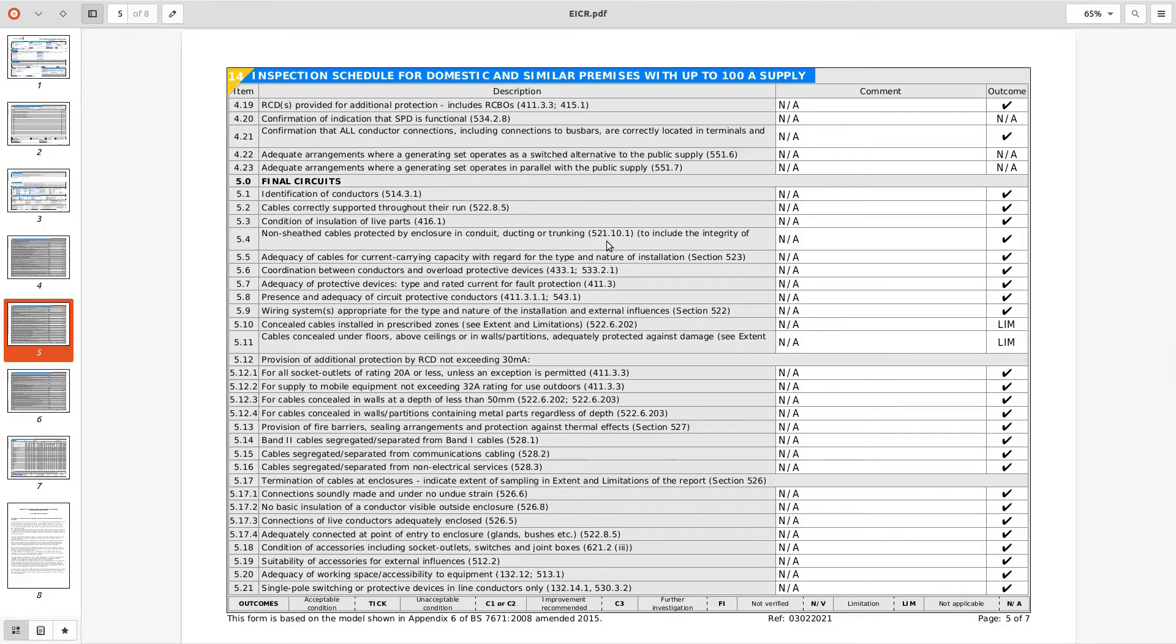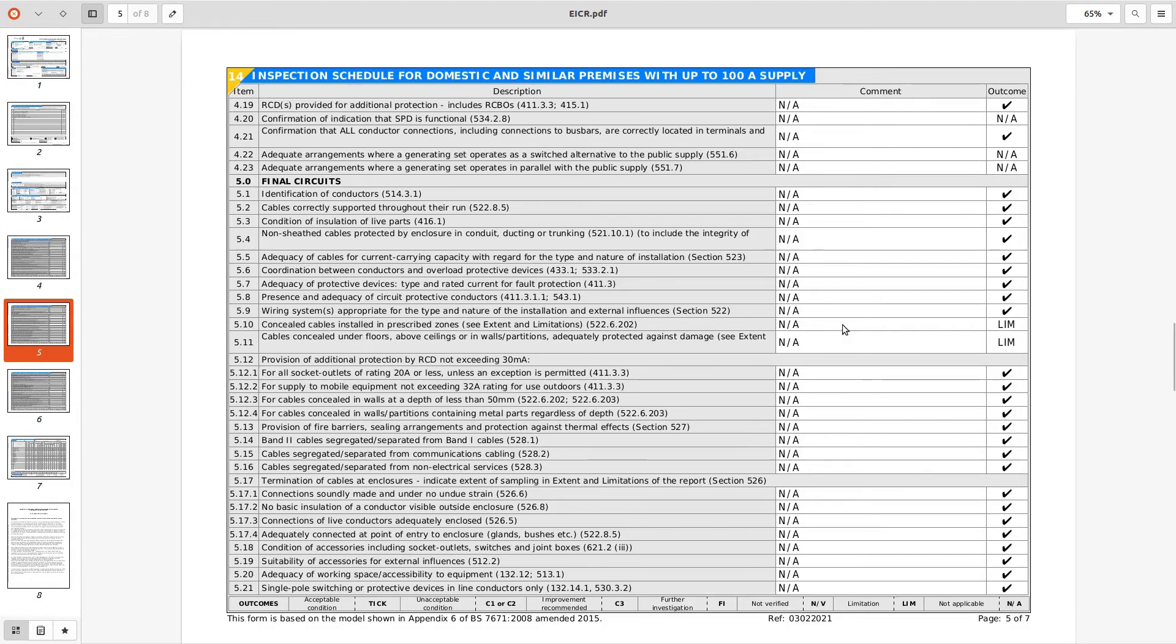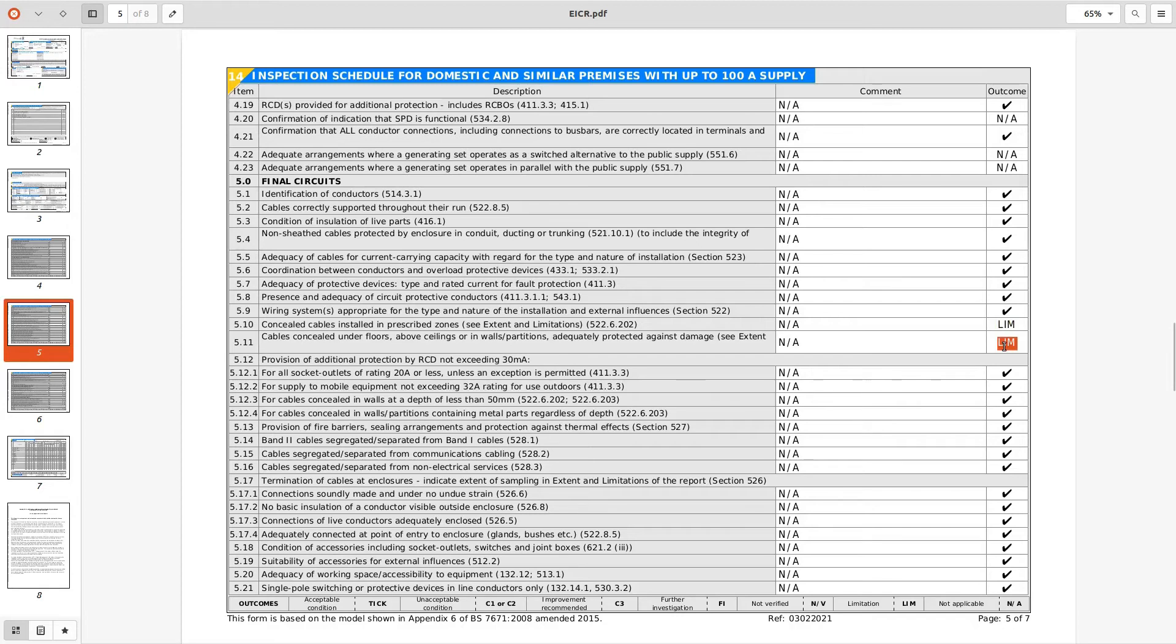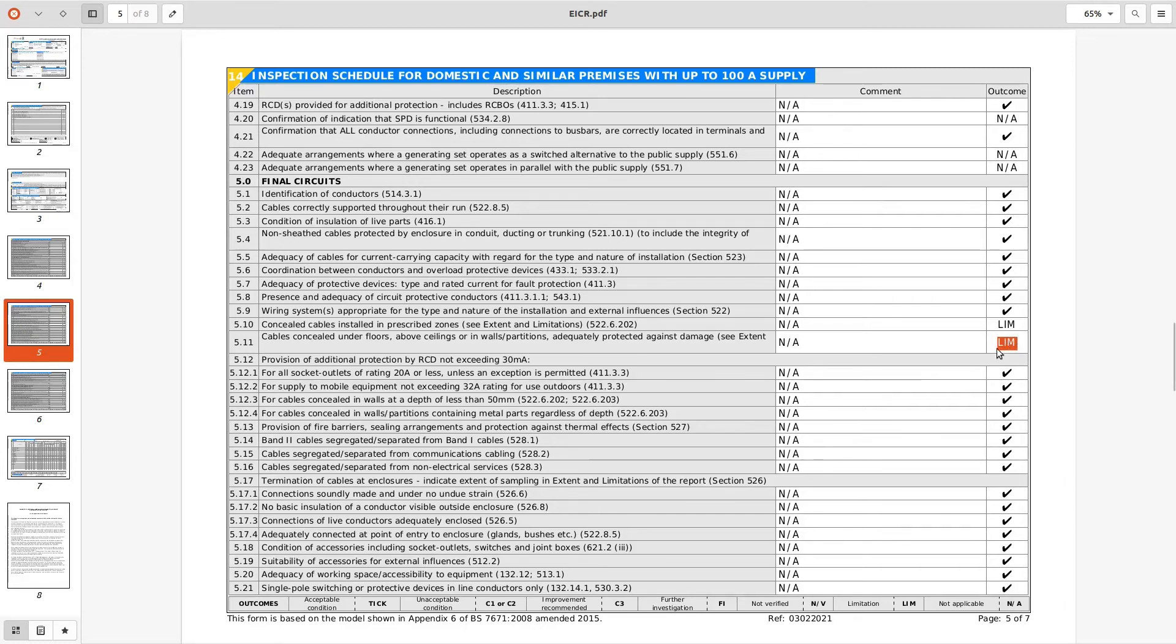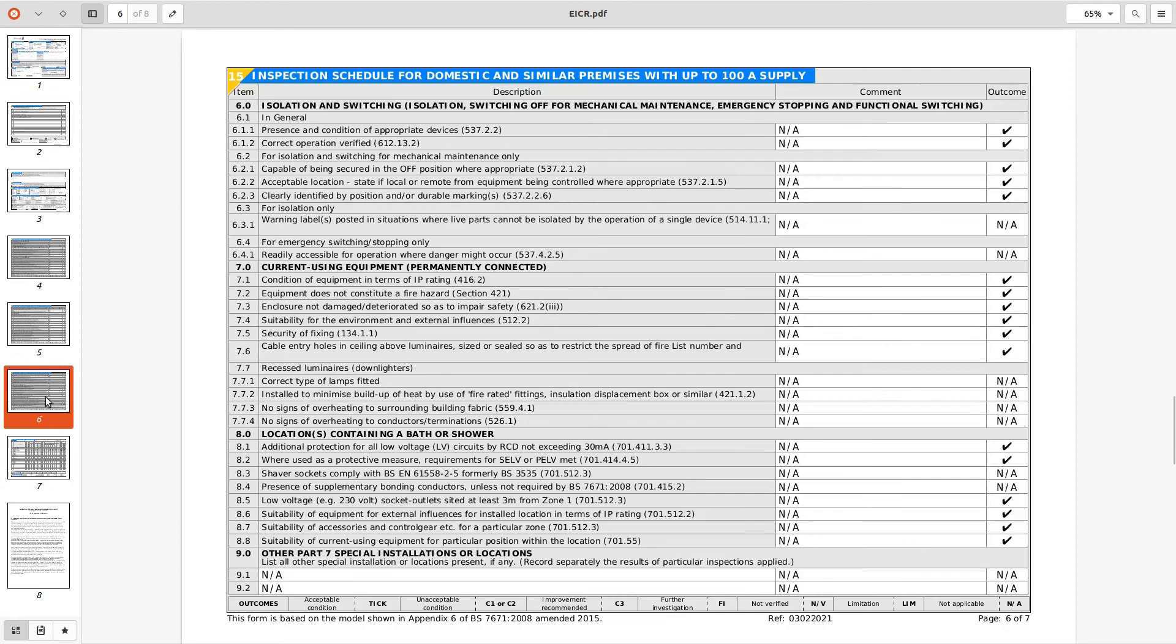Looking through on that that looks pretty good to be honest. Limitations, I'd probably just take these cables installed in prescribed zones annex C extent limitations. Well they're not expecting you to see through the walls, only what you can see, so tick them. And again cables concealed on the floors drop a tick in that box, you know where you've been able to see stuff above ceilings ie in the loft. There was no limitation really was there, was there no loft actually, I don't know we'll have to go to site and have a look at some stage.